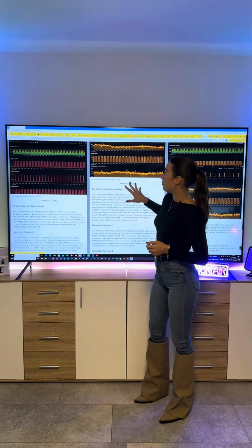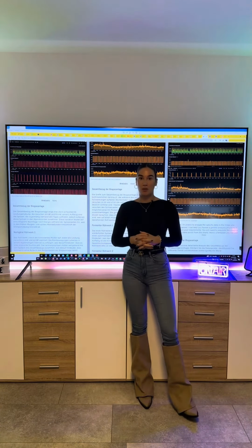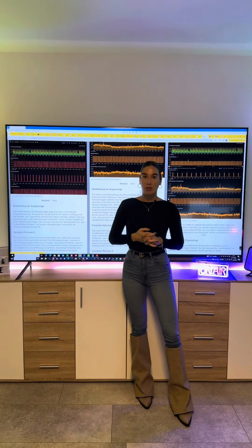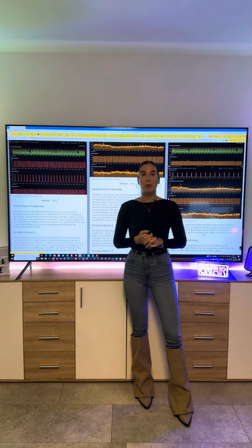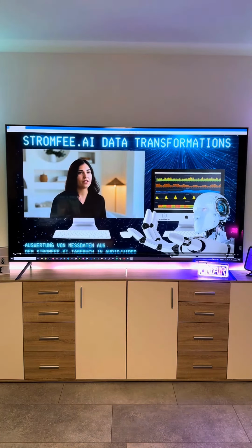And the customer naturally also wants some kind of report. And there we also have different options, once through the video function, but also as a reporting function. And I will show you that again now. The main causes of the peak loads in the biogas plant are attributed to the operation of the stirrers, particularly stirrer 1. The data analysis shows that stirrer 1 correlates most strongly with the peak loads of the overall consumption of the biogas plant at night.